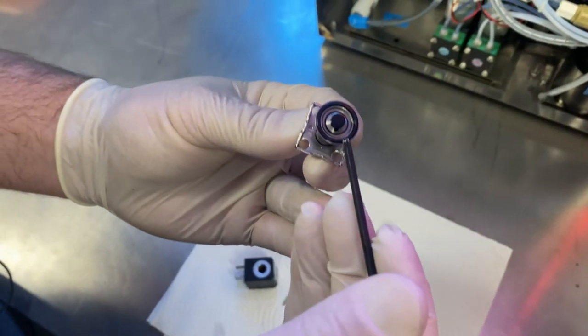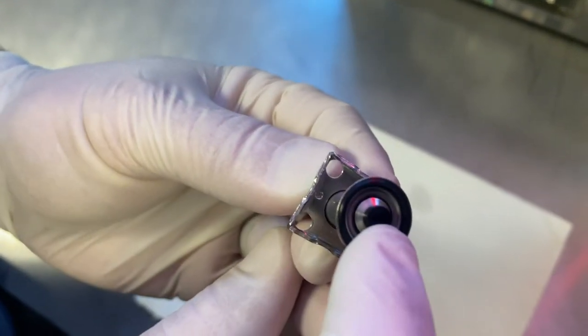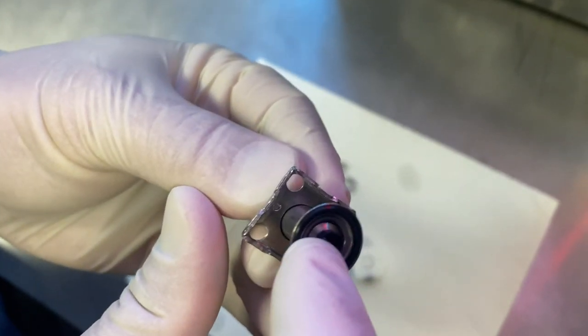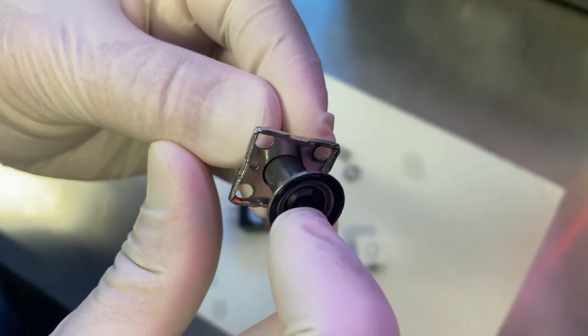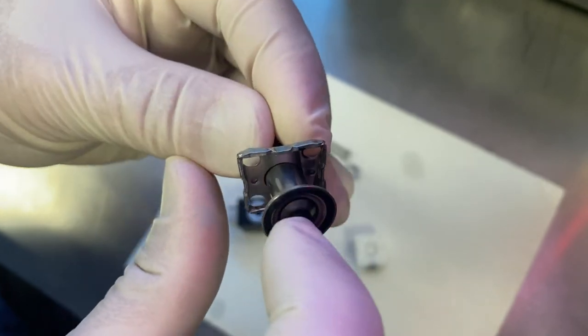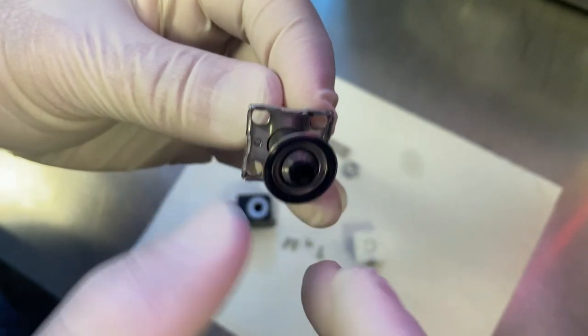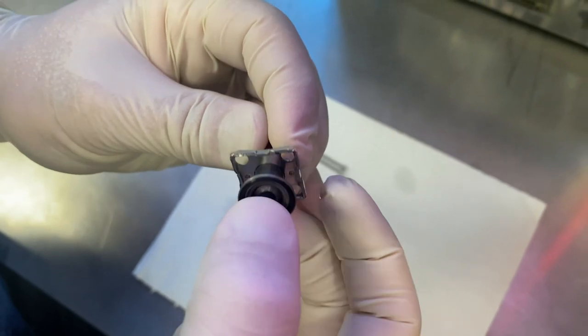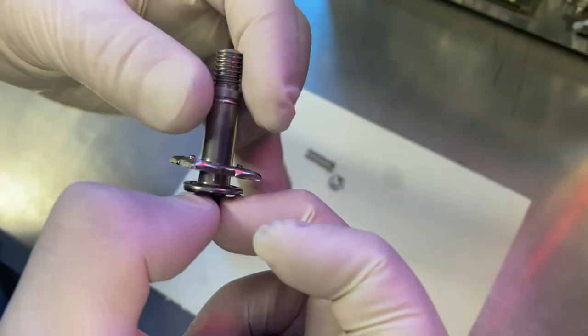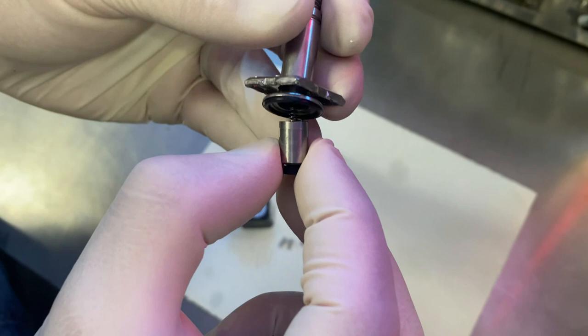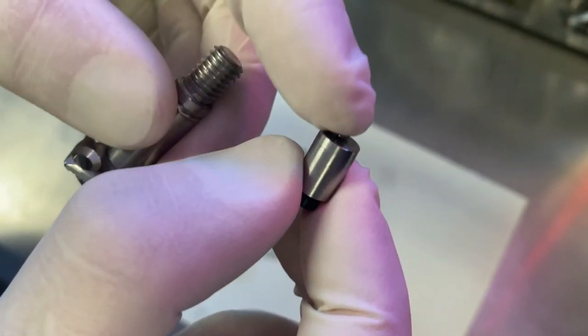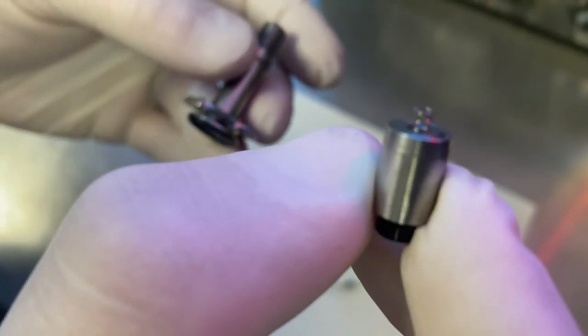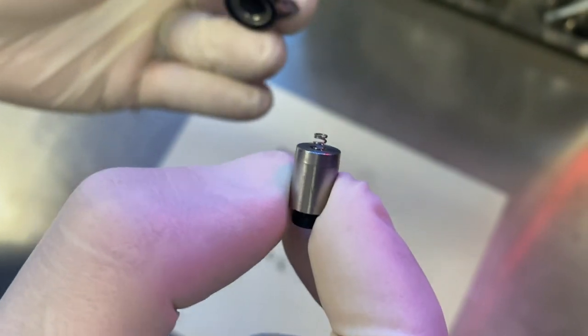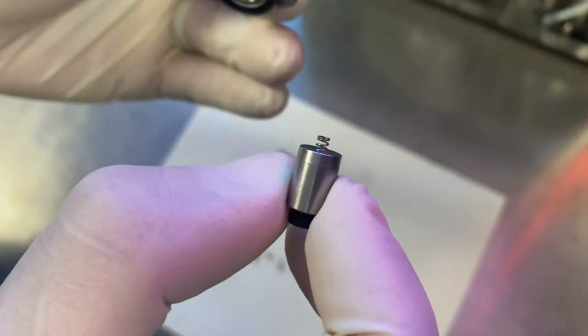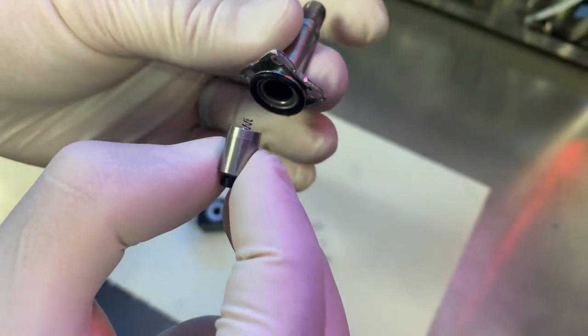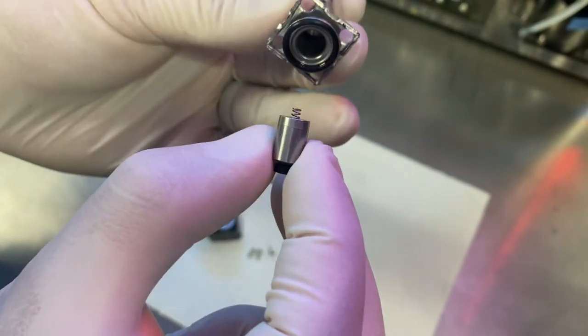You'll see we still have an O-ring right here, and then here's our plunger right in the middle. You'll see that's spring-loaded. Again, it only ever sees makeup, so it'd be really difficult for this to get stuck like an ink valve could. So we'll slide this out really quick and show you the spring. The spring is a main difference here - we just have a little spring in the top of the plunger assembly here. With valve six, you saw a much larger spring on the exterior of the plunger. So that's it, that's all there is to this assembly.